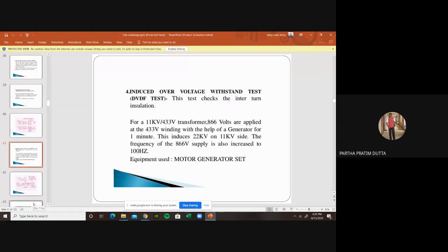Then we come to the induced over voltage withstand test, that is the DVDF, double voltage, double frequency test. It is a very important test. It is usually done as an inter-turn insulation test, to see whether the inter-turn insulation is proper, or whether the core can withstand it. The core has that withstand capacity against double voltage and double frequency. In that case we put double voltage of 11 kV, that means 22 kV, from the 11 kV side, and double frequency, that means 100 hertz, in parallel.